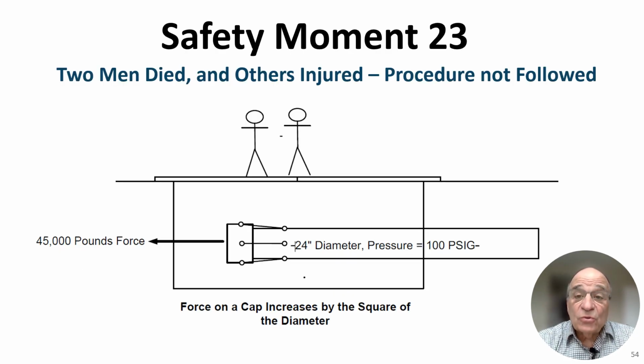Safety moment number 23. 2 men died and others were injured. The procedure was not followed. A 24-inch diameter gas main, newly installed, was being pressure tested, and the procedure was to put a cap on the end of the pressure test piping and then to strap it on using specially designed straps that were to be welded onto the pipe and onto the cap.